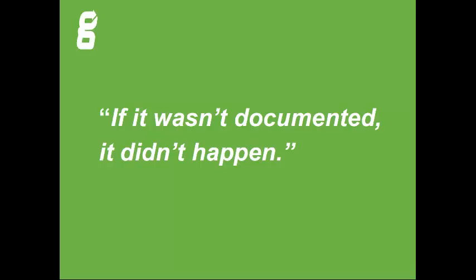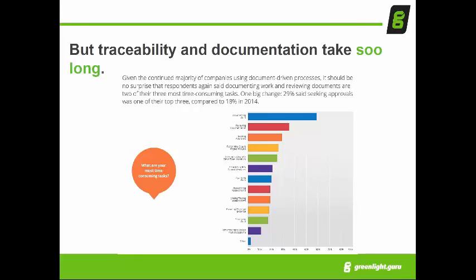I had a manager tell me many years ago that if it wasn't documented, it didn't happen. And if you've ever been across from an ISO auditor or an FDA inspector and you're asked to answer or address a particular question or comment that comes up, they're always going to ask for documented objective evidence. They will never just take your word for it. And so that's a key concept. You have to have documentation in place, and you have to have the assurance that it is in a spot where you know you can find it. It shouldn't be buried on somebody's desk.